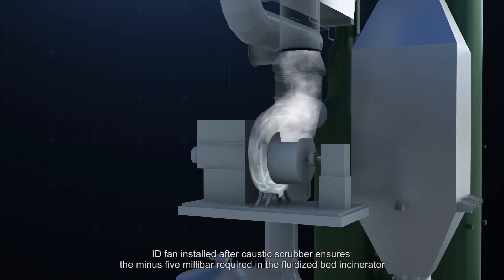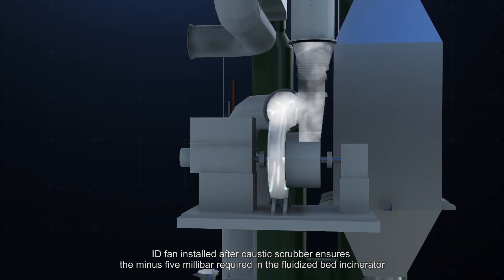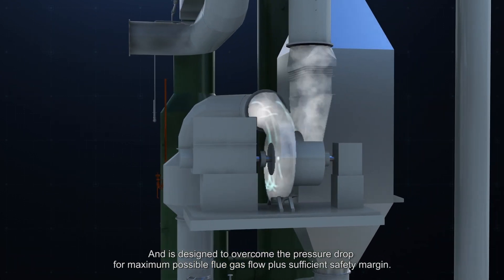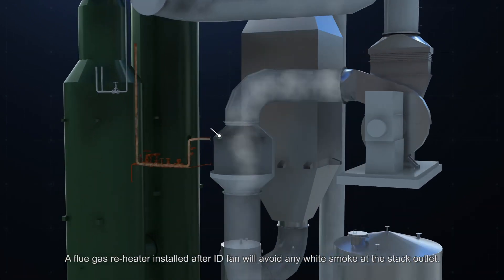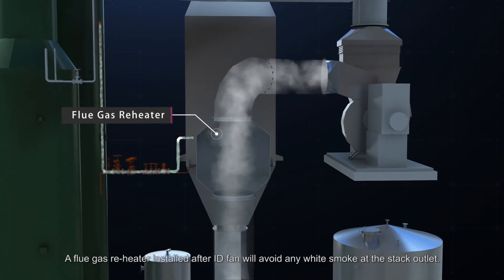ID fan installed after caustic scrubber ensures the minus 5 mb required in the fluidized bed incinerator and is designed to overcome the pressure drop for maximum possible flue gas flow plus sufficient safety margin. A flue gas reheater installed after ID fan will avoid any white smoke at the stack outlet.